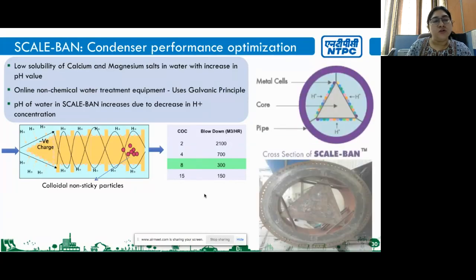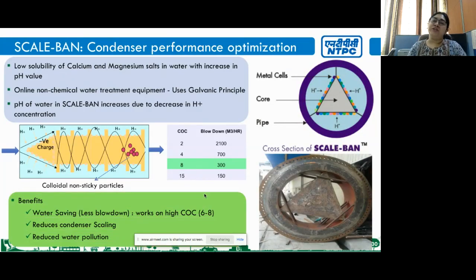We have also installed this SCALE-BAN in our stage 2 units. This is basically a mechanical device to reduce formation of scales in condenser. What it does is it uses galvanic principle. It decreases H positive ion concentration in the water, making its pH increase. This results in precipitation of calcium and magnesium salts before going to condenser, and this gives us a COC of 6 to 8. Earlier, we used to run our units on 3 to 4 COC. Now we have reached a COC of 6 to 7. This reduces condenser scaling and reduces water pollution.